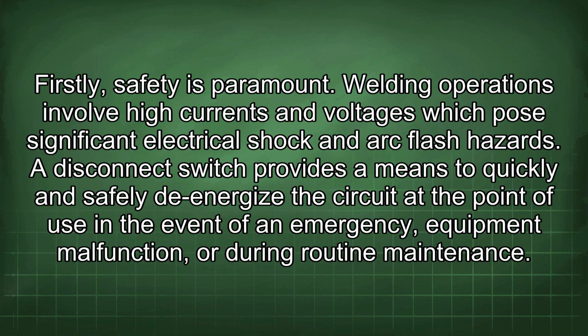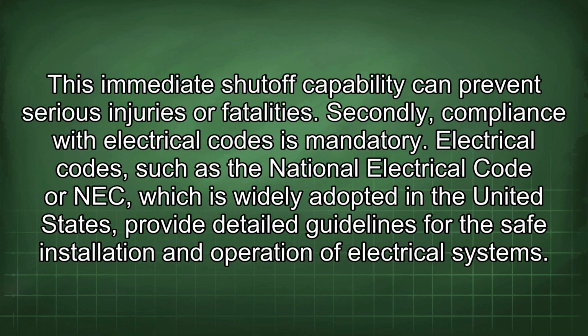A disconnect switch provides a means to quickly and safely de-energize the circuit at the point of use in the event of an emergency, equipment malfunction, or during routine maintenance. This immediate shut-off capability can prevent serious injuries or fatalities. Secondly, compliance with electrical codes is mandatory.